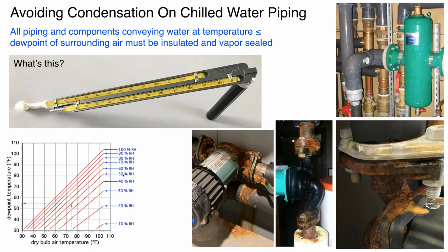I wanted to show you what can happen in hydronic systems carrying chilled water that don't have insulated components. Pump volutes in particular, from what I have seen, are quite prone to oxidation. Now, these pumps are all still operating fine, but you can see, especially this one here in the middle, this is actually only 2 seasons of chilled water cooling, and that's in upstate New York.